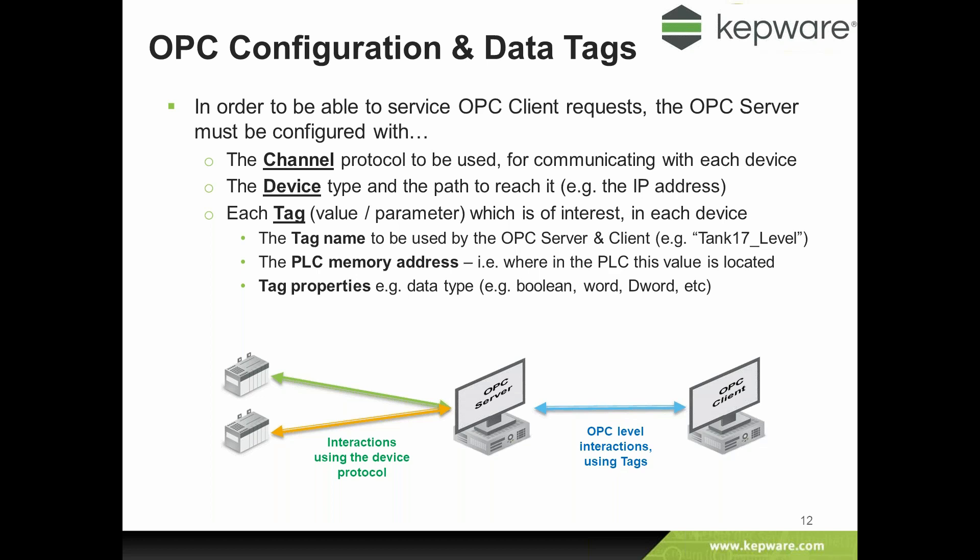Once that's been configured, the OPC client can make requests using the tag syntax to the OPC server. The OPC server resolves that to a particular device on a particular channel and a particular register in that device to get the value out. The OPC server polls for that value, gets the response, and returns that response to the OPC client.